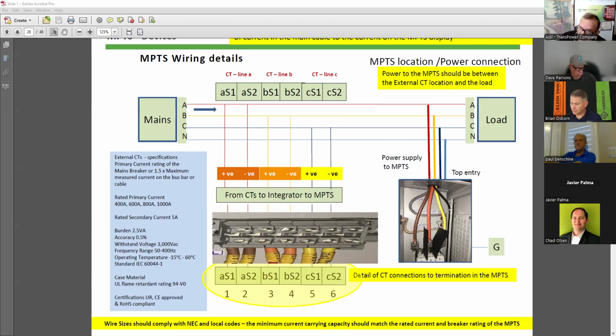Because you cannot take a shutdown, people will try to swap the wires like they do in motors to change the direction. But can anybody here tell me why you shouldn't do that? Why you should not rotate the phases to reverse a motor? Yes, you're going to mix up the phase configuration of the system as far as color coding. Is that what you're looking for?